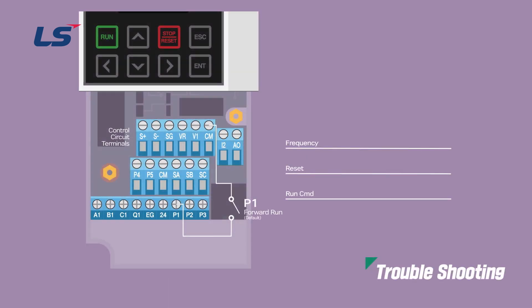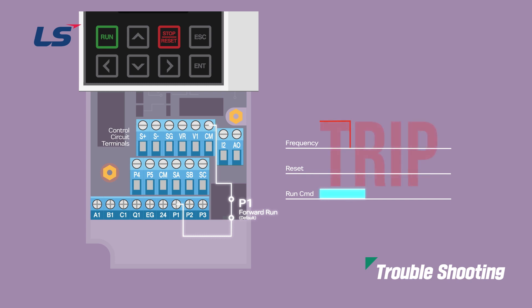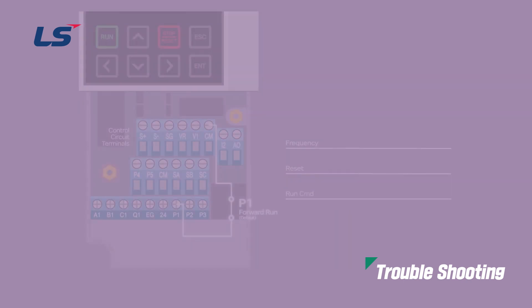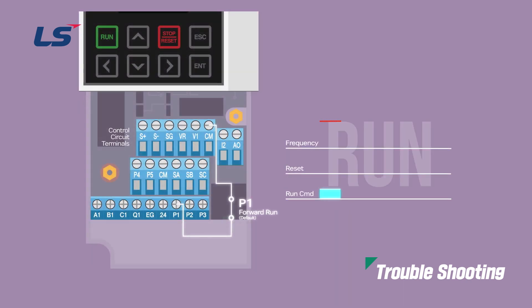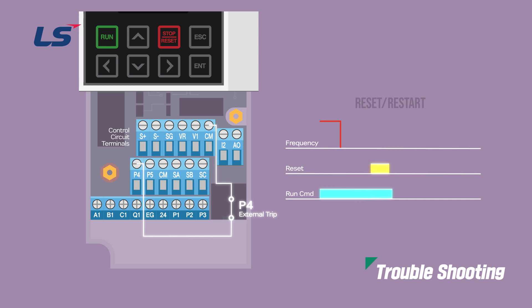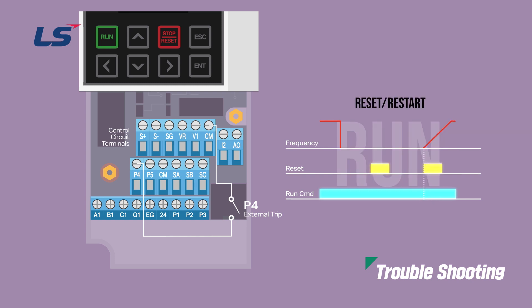Let's look at what to check when the Auto Restart feature is not working properly. First, the Reset and Restart function will only work properly if the Terminal Block Operation command is turned on. If terminal commands are turned off, the feature will not work, so be sure to check that. Also, even if the P4 terminal set as External Trip is still short-circuited, it will not be restarted due to the trip state, so be sure to open it after generating an External Trip.